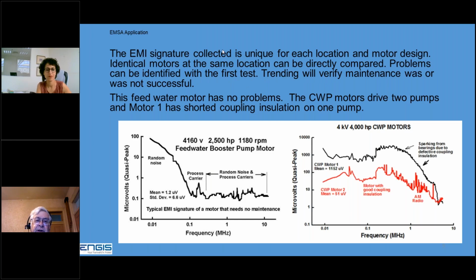The signature that's collected is unique for each location and motor design. Identical motors will have very similar signatures, and if they're at the same location, they can be directly compared. Problems are identified with the first test. Trending will then verify maintenance was or was not successful, and we'll show examples of that later. The feed water motor here has no problems.